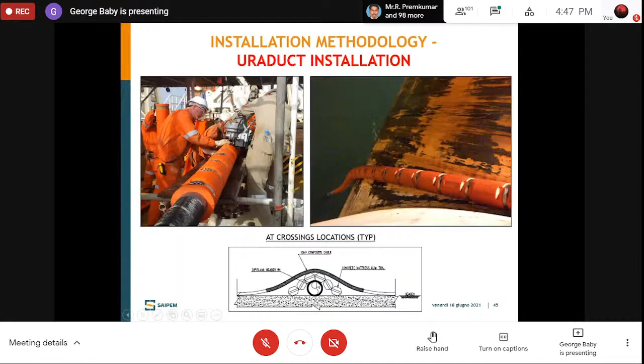As I explained before, when this cable crosses an existing pipeline, we need to maintain a minimum distance from the asset, because if the cable touches the pipeline it will cause an eddy current, which will cause corrosion of the pipeline. To avoid this, we put a concrete mattress on top, and the cable is laid on top of it. This is the preparatory work done before we lay the cable.